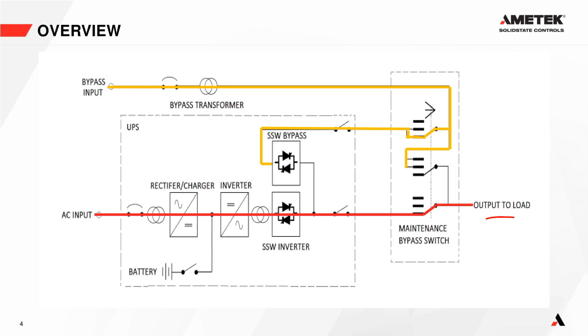It will try and keep the power flow through the inverter as much as it can, because the inverter creates a perfect sine wave that is unaffected by anything that goes on at the AC input or the bypass input. It takes the DC, converts it into AC, and creates a sine wave that the load circuits can use for uninterrupted power.